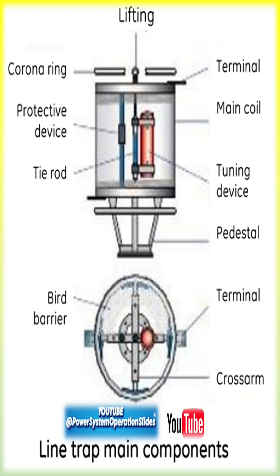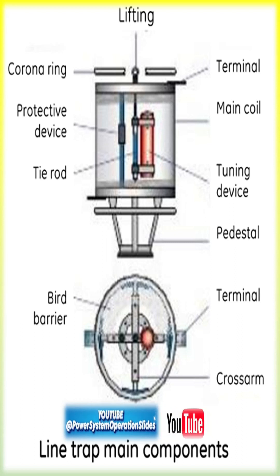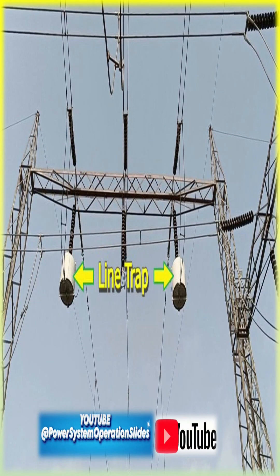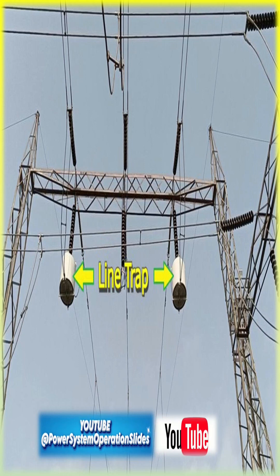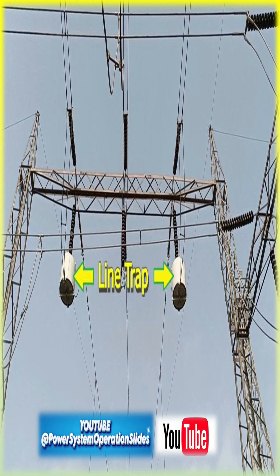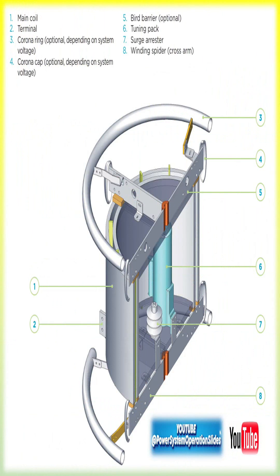The wavetrap acts as a band-stop filter or a high-frequency choke. It blocks the high-frequency communication signals from passing into unwanted parts of the network — such as transformer windings, busbars, or adjacent lines — where they could get dissipated or cause disturbances. That's why we use wavetraps.